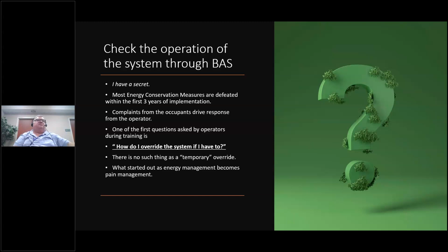When I was doing controls and energy management, and they're looking into a new system, they want to know how to override it. But there's no such thing as a temporary override. If they find a solution outside the operating parameter, it's going to stay in. They'll put it in override through the building automation, or put it in hand, or manually position the flow, the pump, the drive, so it constantly runs at that point no matter what. What started out as energy management becomes pain management. They want the phone to stop ringing, they want to put that aside. And it's day to day. A lot of people get angry, they don't like the way the system works. Especially if people looking at the money and how much it costs to put this in, and it doesn't work, then it really gets ugly. So part of your solution is also to make somebody happy.